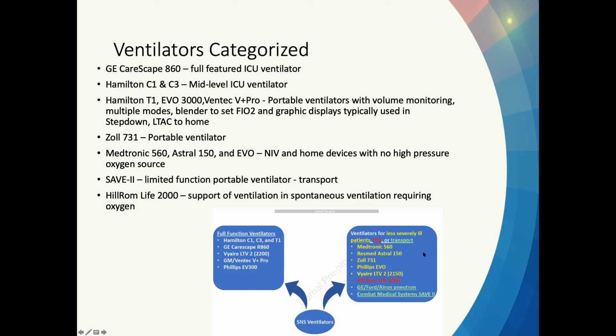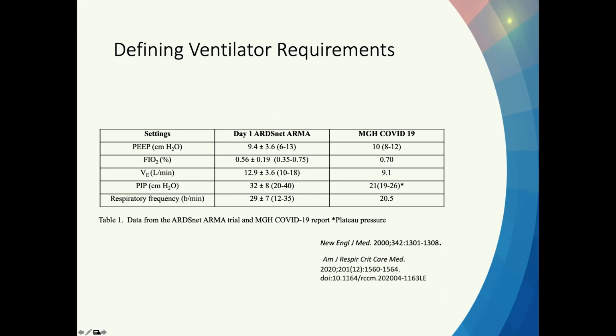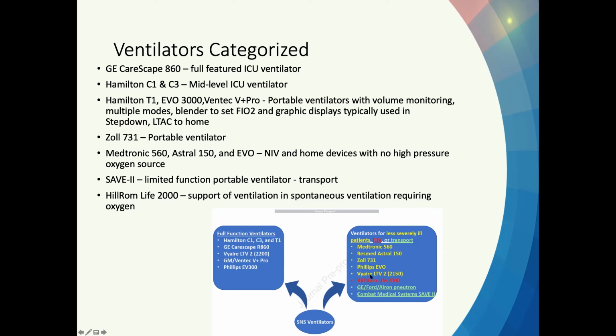But on this side, some of these ventilators were essentially made for non-invasive ventilation. The formerly Puritan Bennett, now Medtronic 560, the Astral, and the Philips Evo, being different from the EV300, doesn't have a blender and has other limitations, and the 2150 as well. The Zoll 731 is a portable ventilator the military uses and is very capable, but doesn't have the displays of pressure, volume, and flow, and performance-wise isn't necessarily comparable to these in terms of delivery of gas and triggering spontaneous breathing. And then the Hillrom device is the old Breathe device. It was meant to clip on your belt and help a patient with COPD who's ambulating not get short of breath. I have no idea why they bought those.